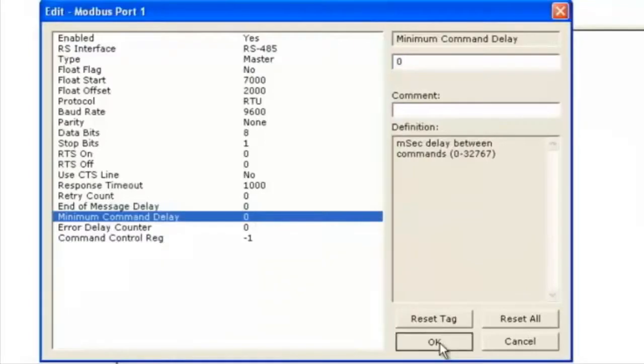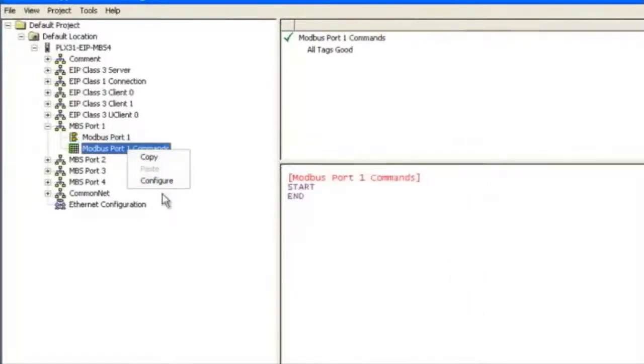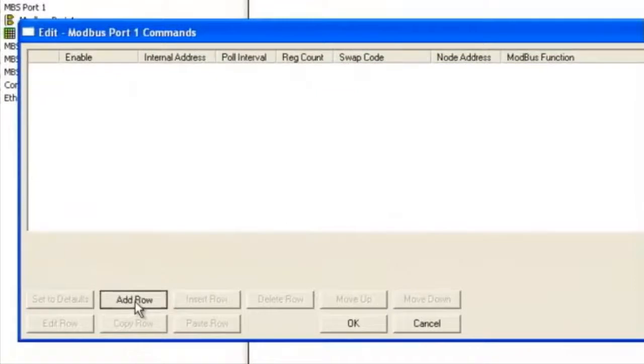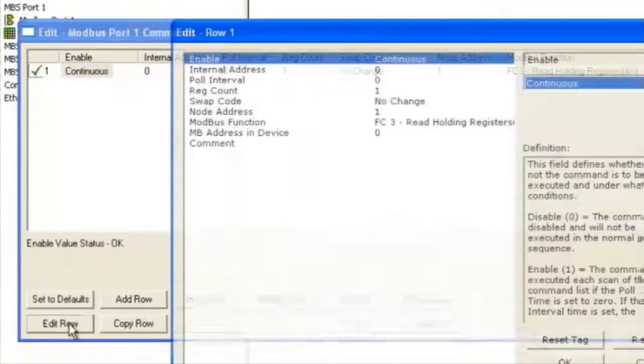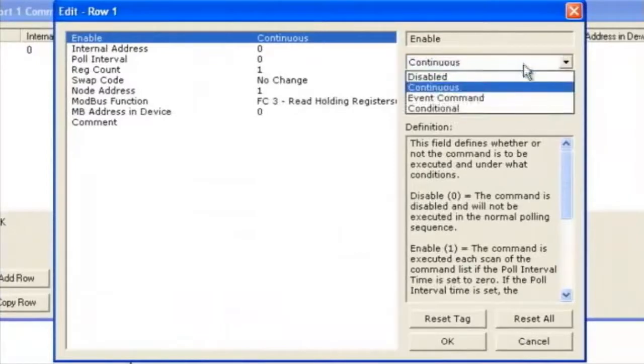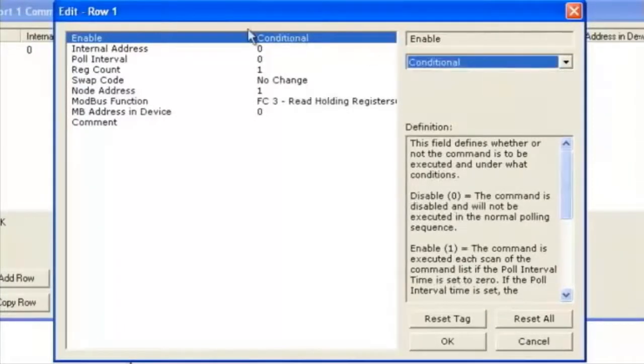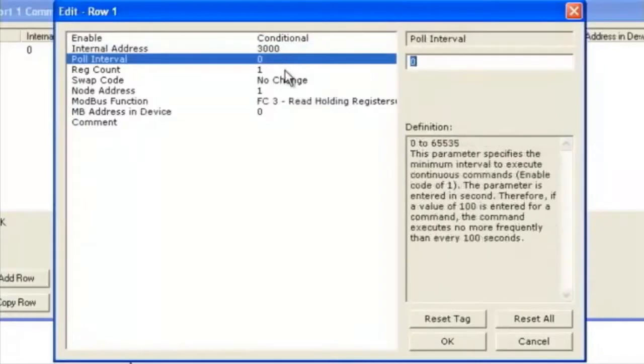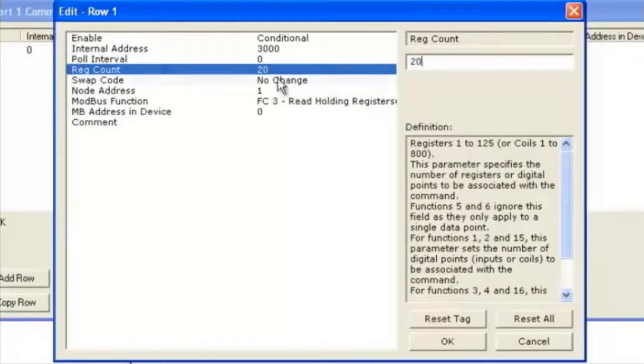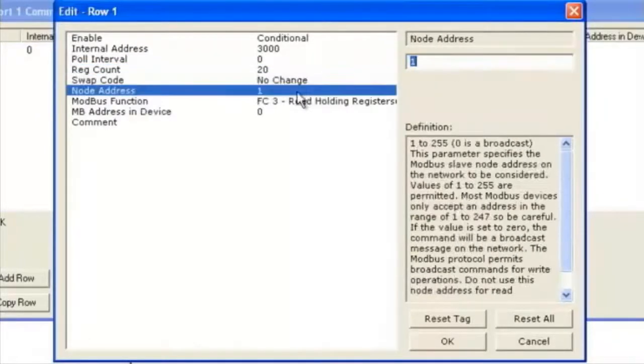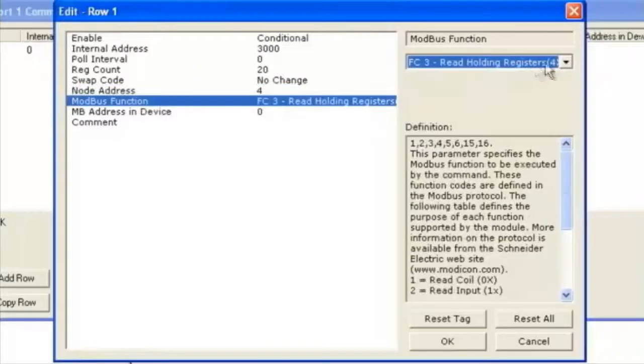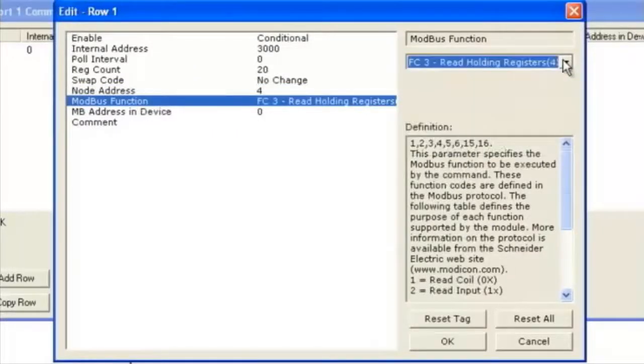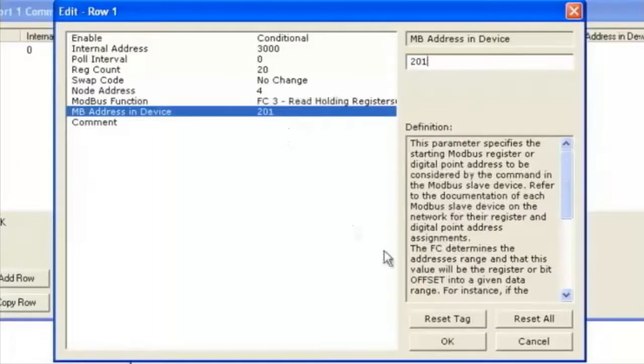Next we'll configure the port 1 commands. This is where we're going to build a command for port 1. We'll click add a row and edit that row. First one is continuous because we want this command to continue to pull. Internal database is 3000. We'll leave the pull interval at 0. Register count is 20 words. Swap code we'll leave at no change. Node address will be 4. We're going to choose function code 3. The Modbus address in the device is 201. We'll click OK. This completes adding a command to Modbus port 1.